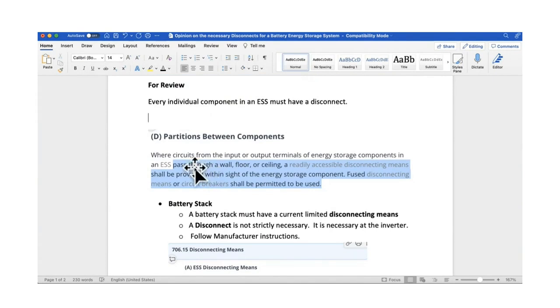And so there's a difference between the energy storage system disconnect. So that would be the disconnect of the whole system. And so the energy storage system disconnect, in my opinion, would be an AC disconnect. But then there's also the question that's a little bit unclear about what we would call an equipment disconnect when we're looking at Article 690. Sometimes too, what I like to do is when something's not clear in 706 to look in 690 because there's a lot of similarities in there.